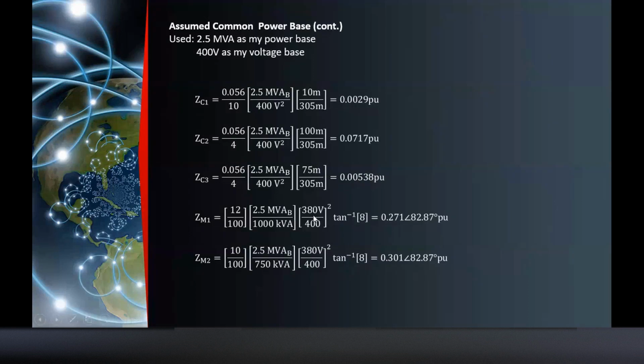Then, the voltage rating of your motor is 380. Definitely, the 12% will change when rated at 400. So you will find the new reactance based on the 400 volts tapping point. Then find the inverse tangent of the short circuit power factor of that motor. You will get 0.271 angle 82.87 degrees per unit.